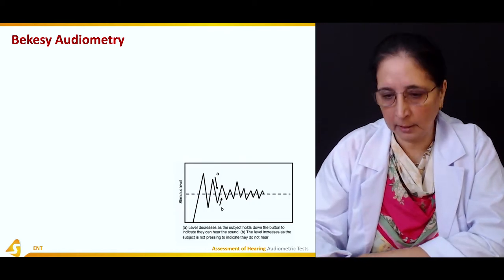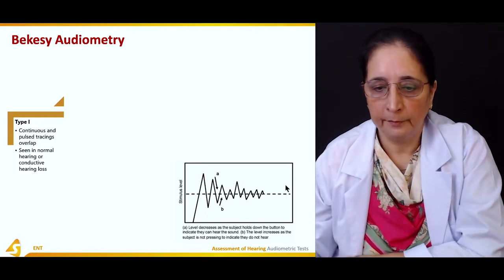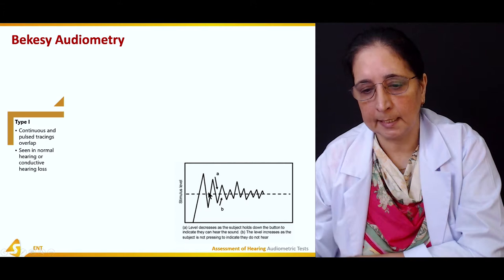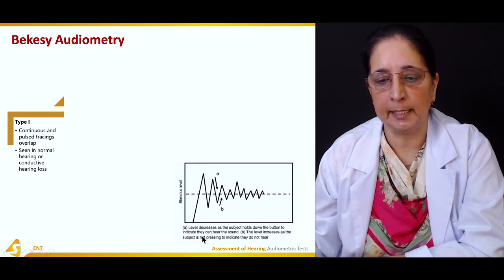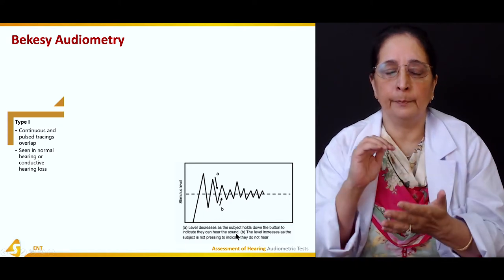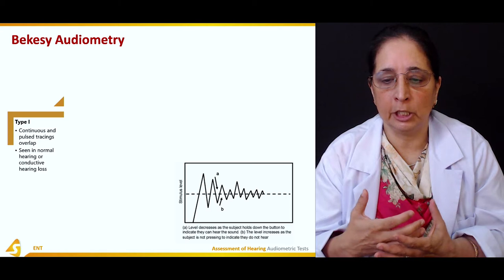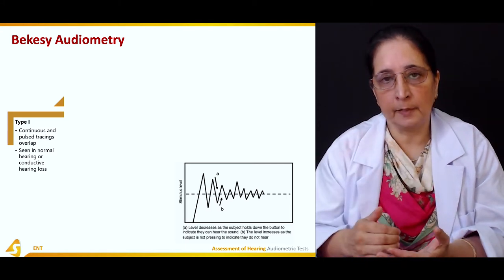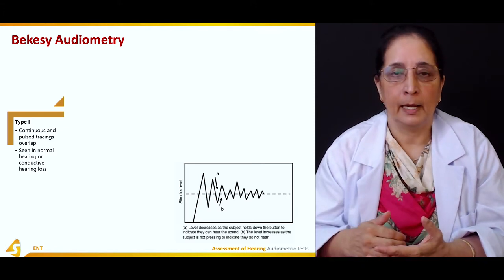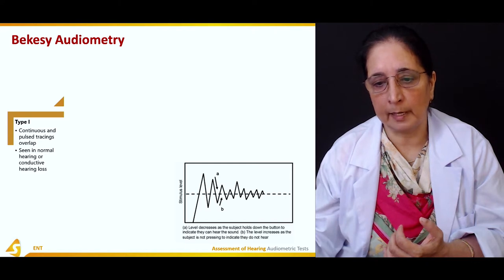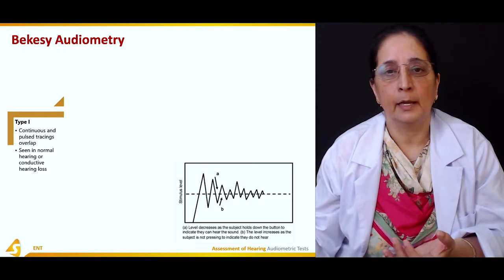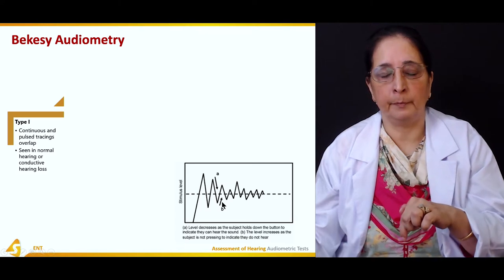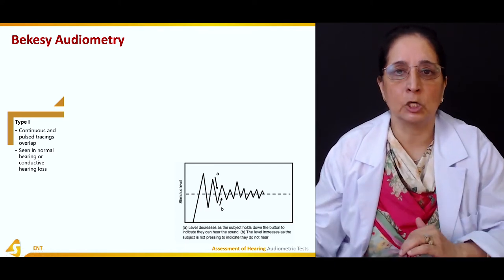In Bekesy audiometry, the stimulus level is the baseline. When the patient presses the button to indicate they can hear the sound, the level decreases. When the button is not pressed — meaning they cannot hear — the level increases. So, decreased level corresponds to button pressed, and increased level corresponds to button not pressed.